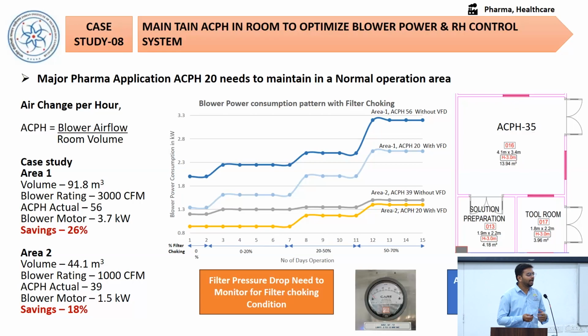Once our air filters are choked, the AHU is equipped with multiple sizes of filters. So whenever our air filters are choked, it increases our blower power. To maintain that ACPH, blowers are designed to maintain ACPH even at the full choking of the filter. So all blowers always have a higher design than is required.